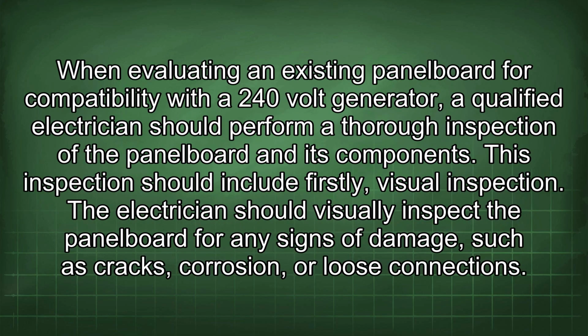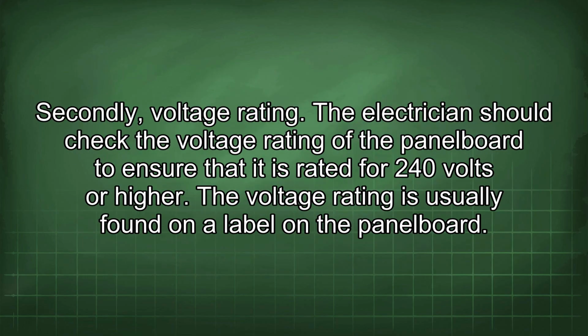When evaluating an existing panel board for compatibility with the 240-volt generator, a qualified electrician should perform a thorough inspection of the panel board and its components. This inspection should include, firstly, visual inspection. The electrician should visually inspect the panel board for any signs of damage, such as cracks, corrosion, or loose connections. Secondly, voltage rating. The electrician should check the voltage rating of the panel board to ensure that it is rated for 240 volts or higher. The voltage rating is usually found on a label on the panel board.